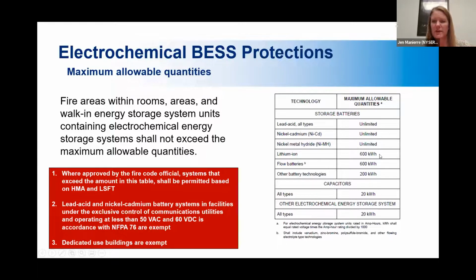And the other exception for this maximum allowable quantities of 600 kilowatt hours for lithium ion batteries, in addition to the fire code official being able to allow larger quantities based on the results of the testing that we talked about on the last 2 slides, is that dedicated use buildings that have nothing in them except for batteries can also exceed those quantities. So if you have batteries in the basement of an office building where there's a bunch of people working, you're going to have to do that hazard mitigation analysis and the large scale fire testing and get that waiver from the code official. If you build a large building out in the middle of nowhere that doesn't have any people in it, or homes nearby or anything like that, just a dedicated use building, nothing but batteries, the code allows the quantities to be more than 600 kilowatt hours.